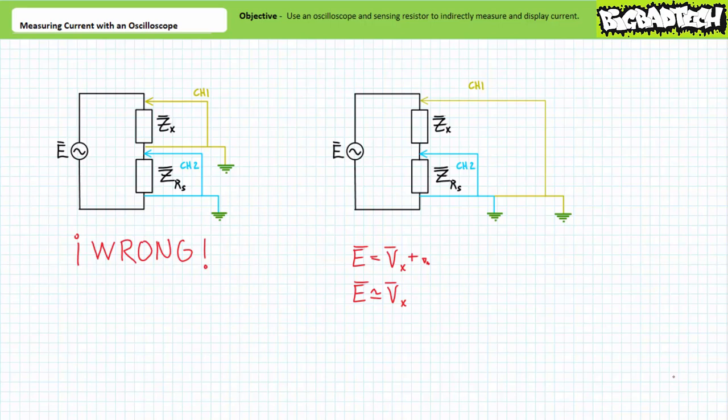Operating under this assumption, the voltage across the element of interest is being measured by channel one. Channel two is measuring that tiny, neglected voltage drop across the tiny sensing resistor. Mathematically we are ignoring it; however, it's still there, and the oscilloscope screen can be appropriately scaled such that this voltage waveform can be displayed and measured. Given current is voltage over impedance, an appropriate scaling factor can be applied to the voltage on channel two to arrive at the resultant current. Additionally, one can simultaneously display both channels to show the relative phase shift of the voltage across the element of interest and the current through it.